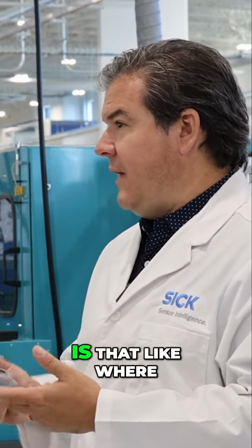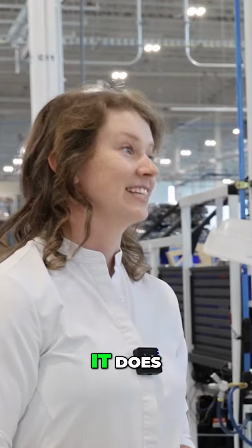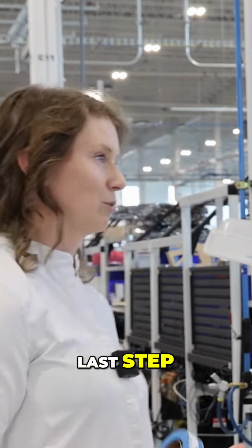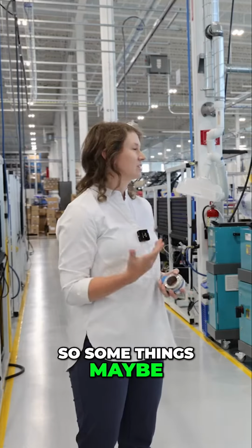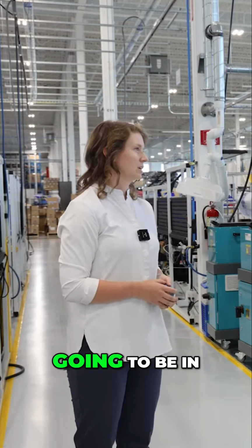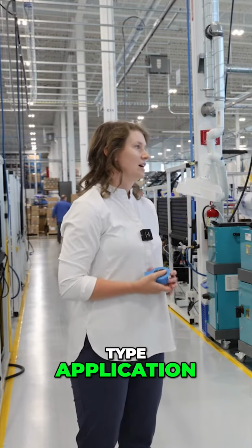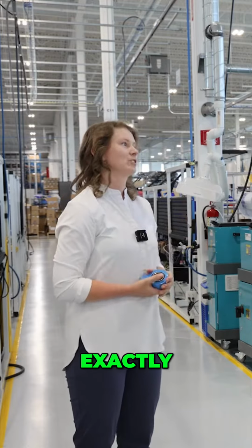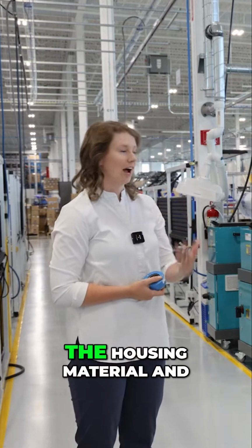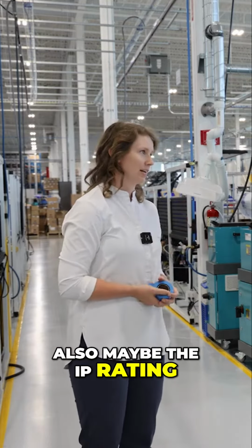What about application? Is that like where it's going to go? Does that matter? It does, yes. So that is the last step really, is to think about those finer points within the application. So some things maybe to consider is, maybe the encoder is going to be in a food and beverage type application. So it's washed down. Exactly. Okay. So in those situations, you want to consider the housing material and also maybe the IP rating.